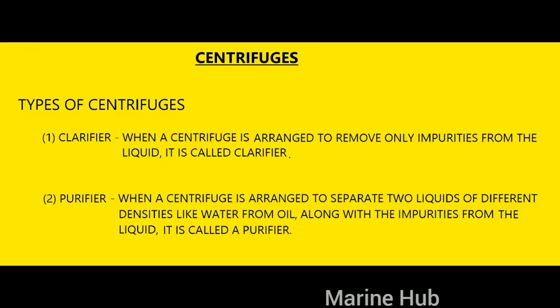Centrifuging is the process by which the effects of gravity can be amplified by the use of centrifugal force, to the extent that the separation process becomes rapid and continuous. Centrifuges work by rapidly spinning a bowl containing the liquid. There are two types of centrifuges based on application: clarifier and purifier.